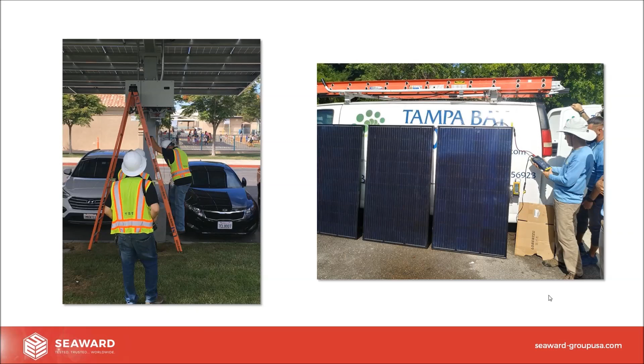Similarly, on the right-hand side, we decided to take some panels off the rooftop and do some testing down by the van side. The flexibility and headroom of this tool, we have 1000 volts maximum at 15 amps short circuit current maximum, means we can string together a single panel or 16 panels, and find out different things about the different configurations of panels, all while taking irradiance and accurate cell temperature readings.